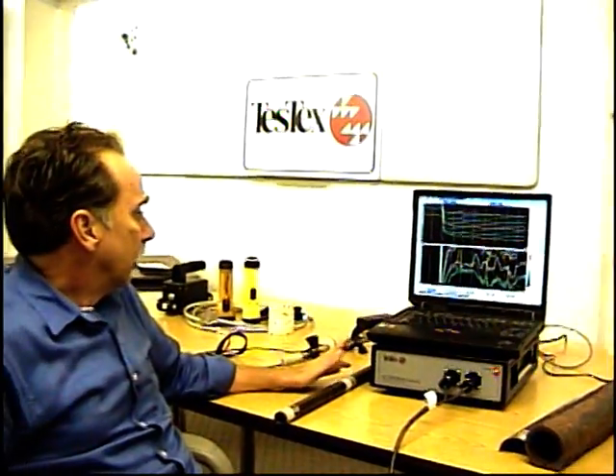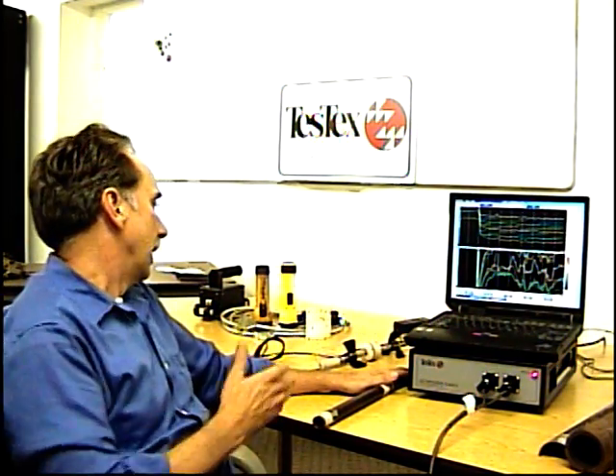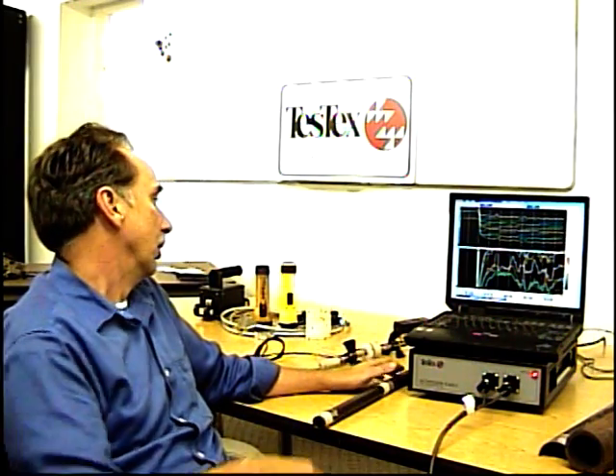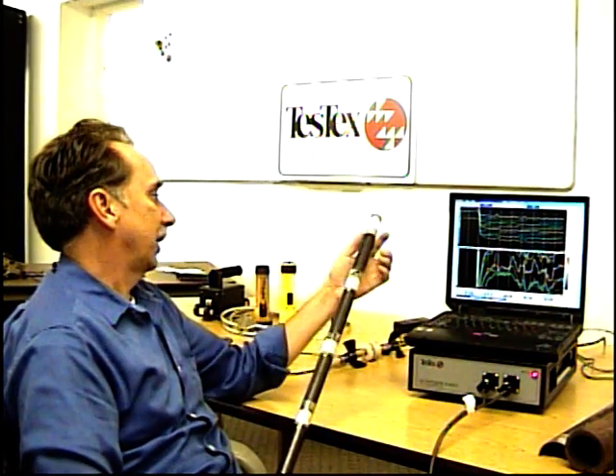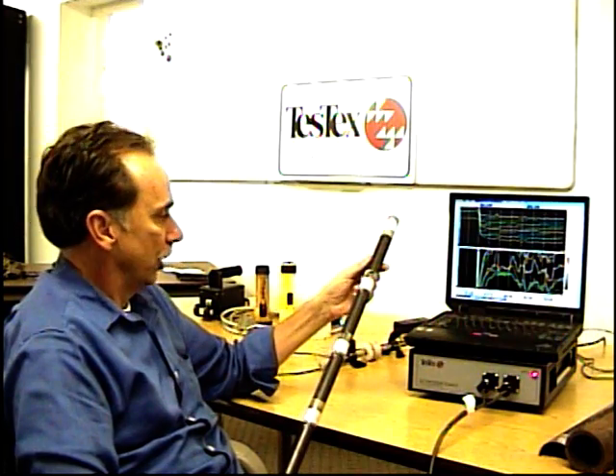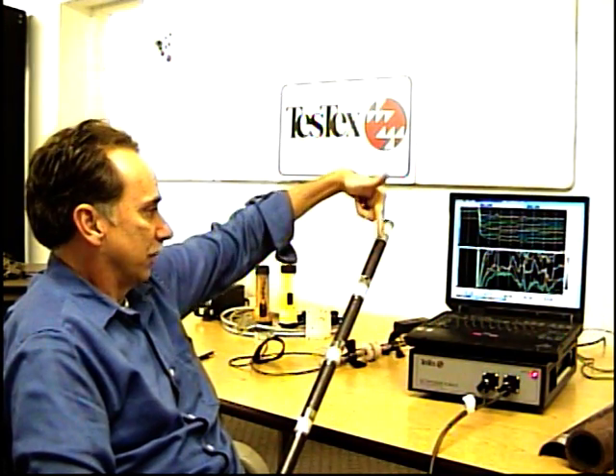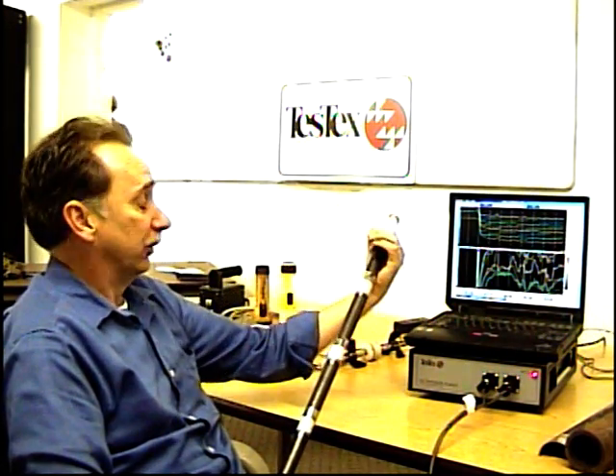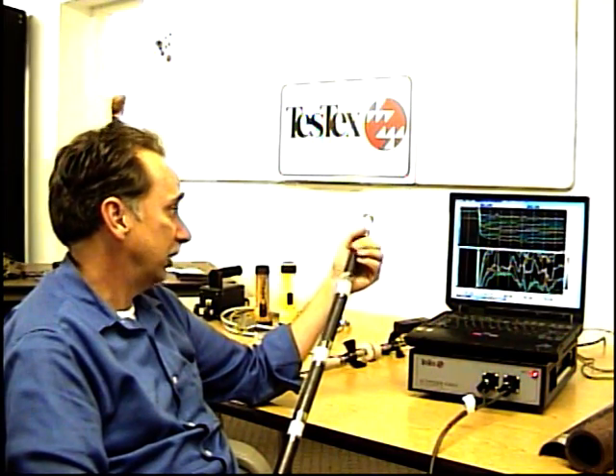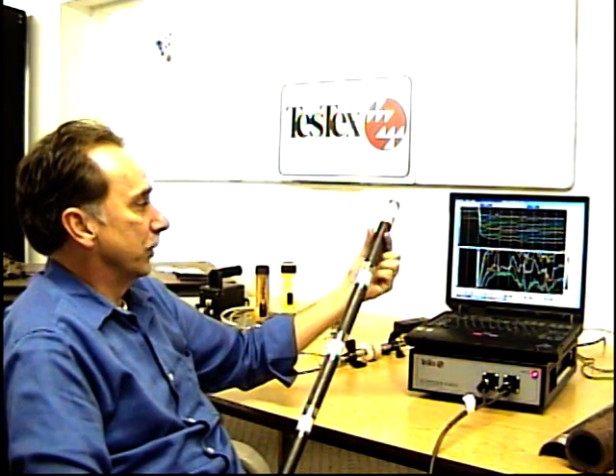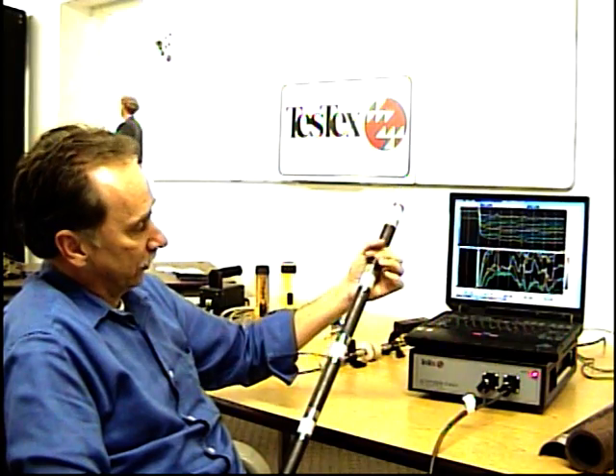Now typically when we go out to do a job, we're just usually pulling single channel, but if we know we're having pits or the customer's having problems with pits, we're going to want to bring our multi-channel probe with us because it's more sensitive to pitting as opposed to our single channel. Now, when you're doing single channel and it's coming down through the length of the tube, it's taking an average because there's only actually one channel. It's doing the full 360 degrees, but it's averaging as it's going down through the whole 360 degrees.